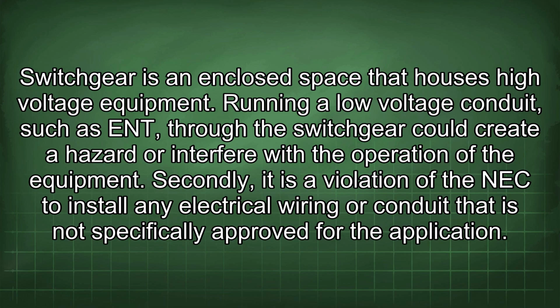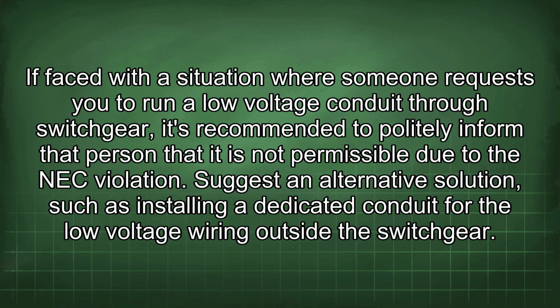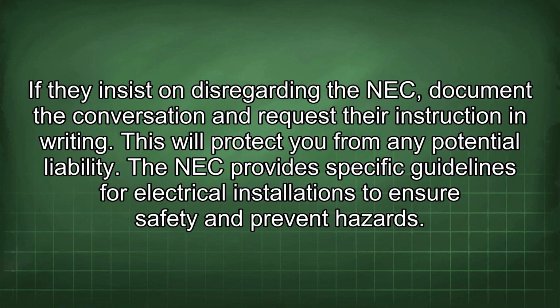the equipment. Secondly, it is a violation of the NEC to install any electrical wiring or conduit that is not specifically approved for the application. If faced with a situation where someone requests you to run a low-voltage conduit through switchgear, it's recommended to politely inform that person that it is not permissible due to the NEC violation. Suggest an alternative solution, such as installing a dedicated conduit for the low-voltage wiring outside the switchgear. If they insist on disregarding the NEC, document the conversation and request their instruction in writing. This will protect you from any potential liability.